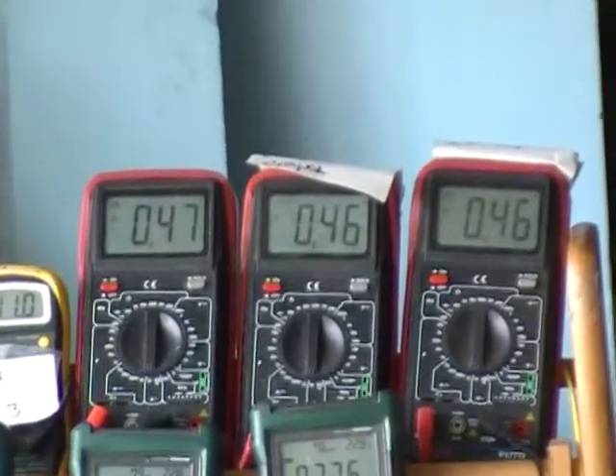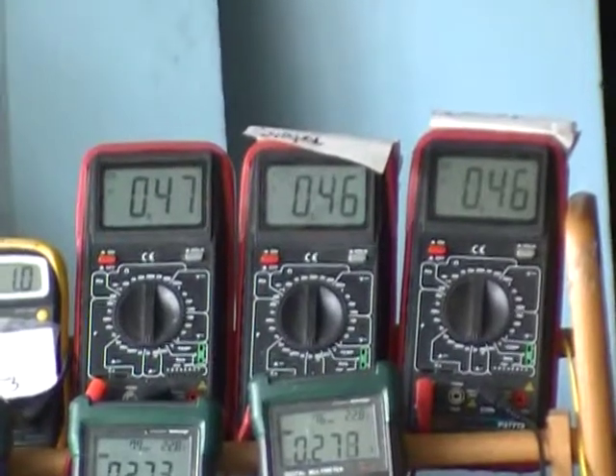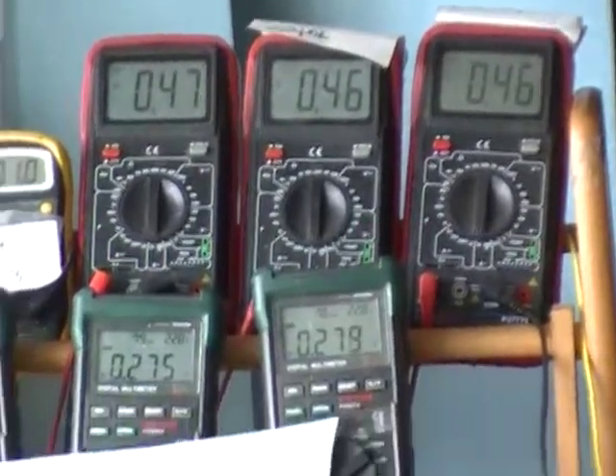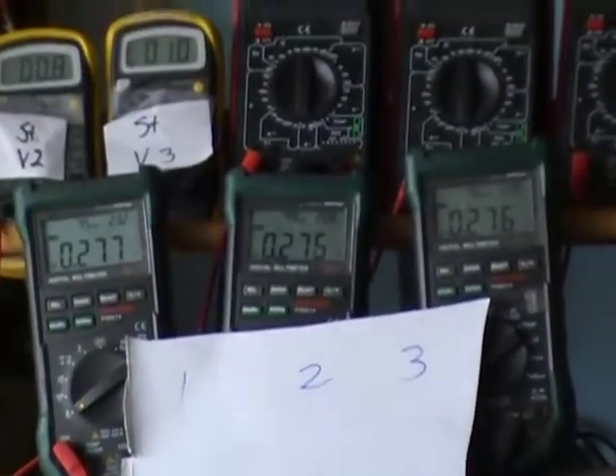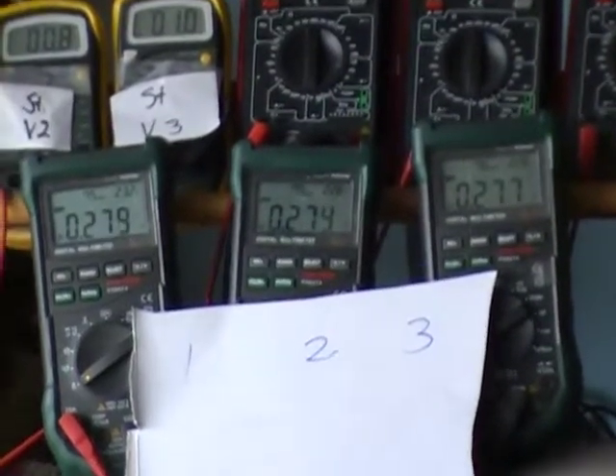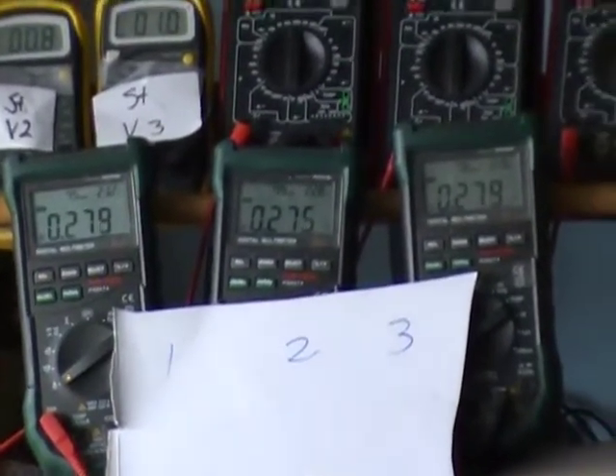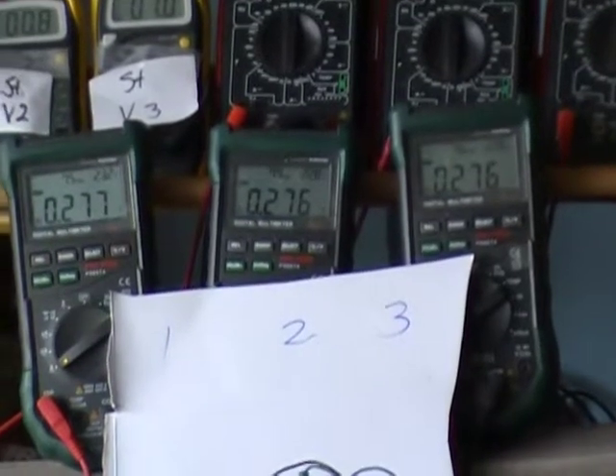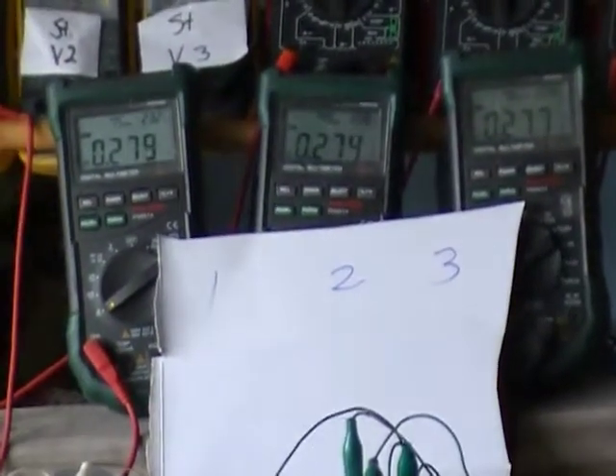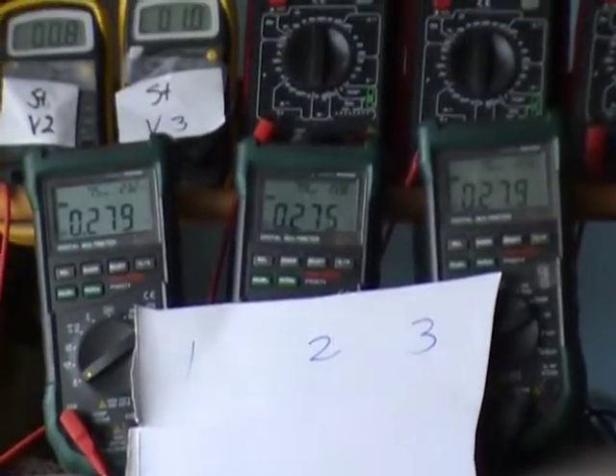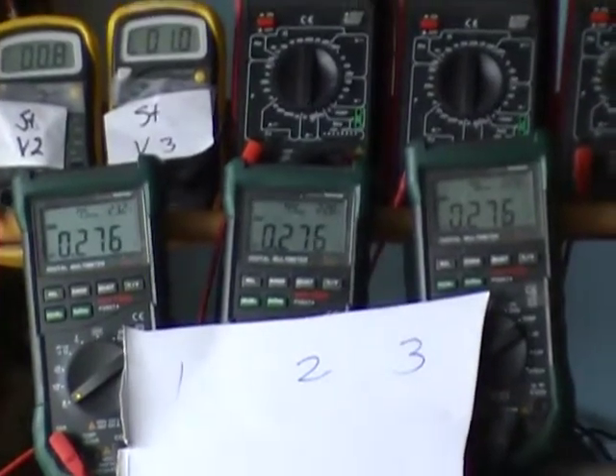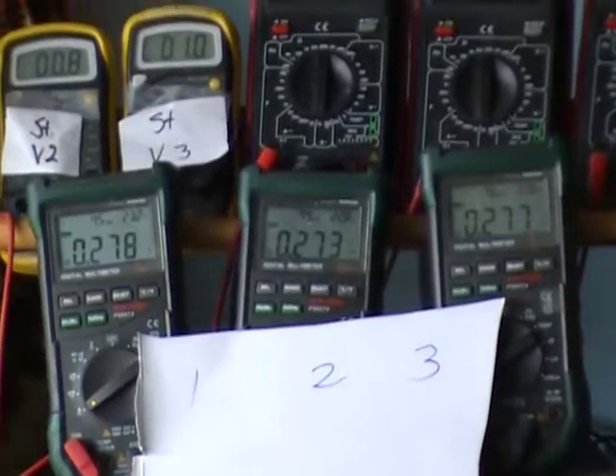Our stator line amperages are 0.47 amps, and below that we have the phase amperages attached in delta: 0.278, 275, 277. You can see the fluctuation of voltage caused by this rotating field vector.